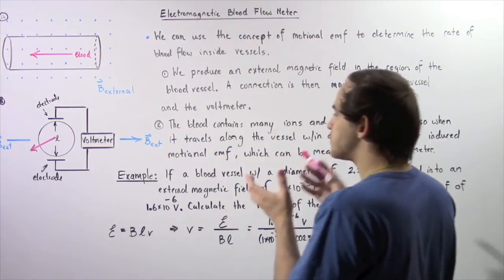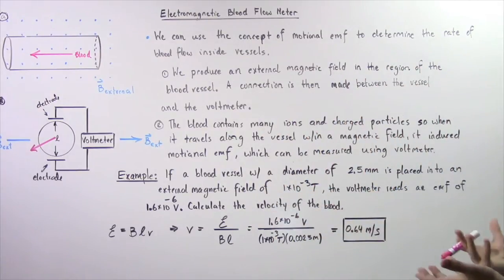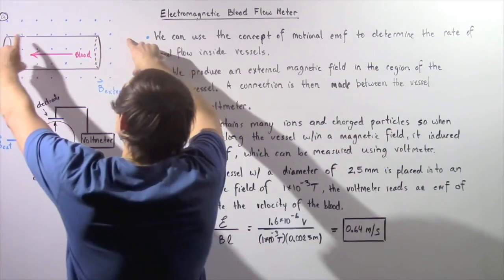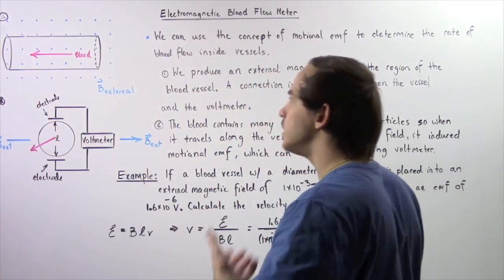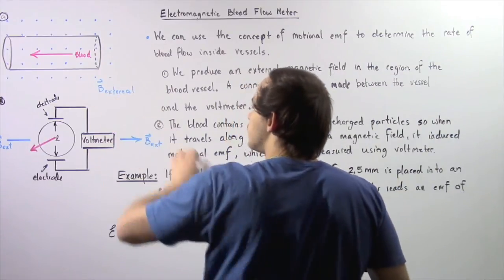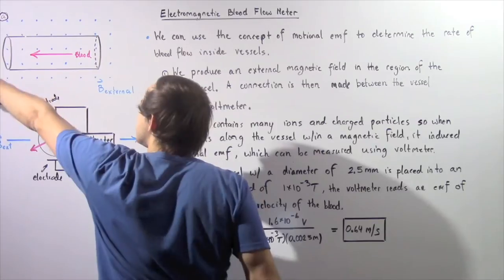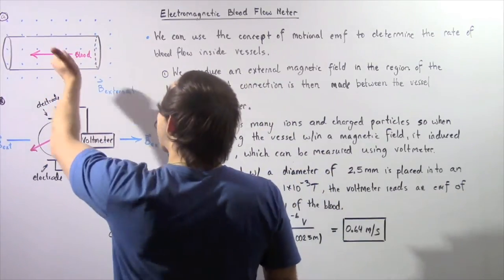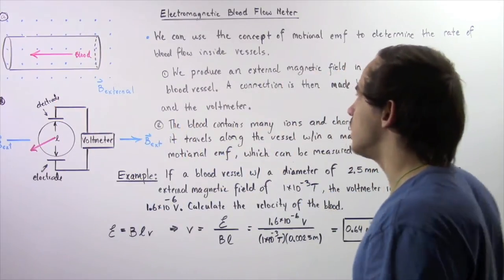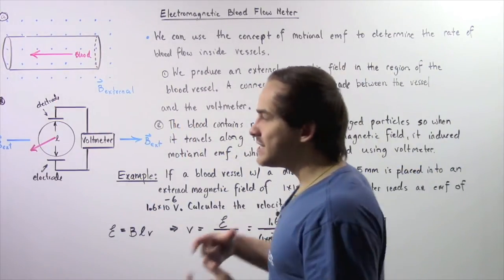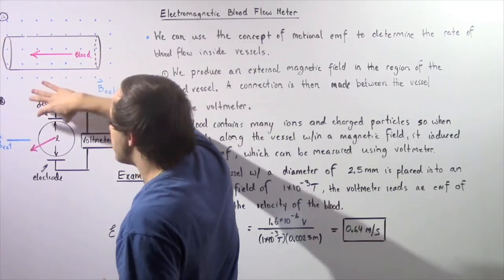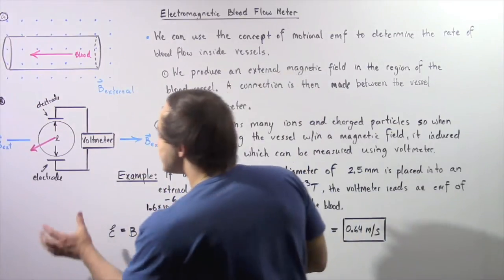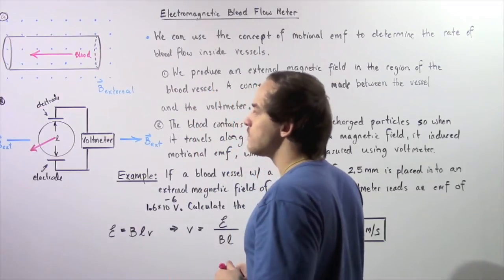Let's look at the two steps we must take to create our Electromagnetic Blood Flow Meter. First, we take our blood vessel and place it into a region that has an external magnetic field given by B. The blood is moving in one direction and the magnetic field points out of the board, as shown by the blue lines. Next, we take two electrodes and place one on the top portion of the blood vessel and the other on the bottom portion.